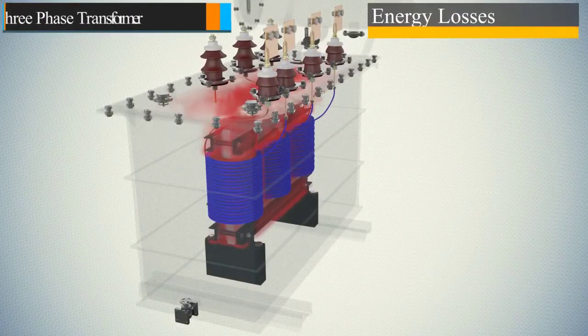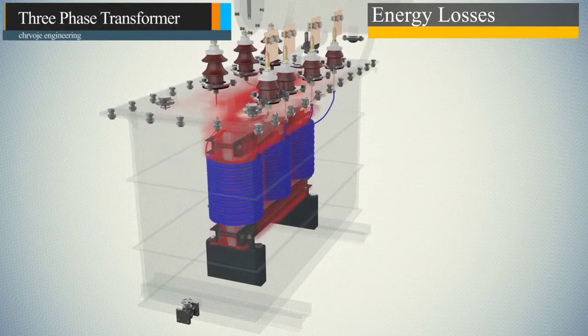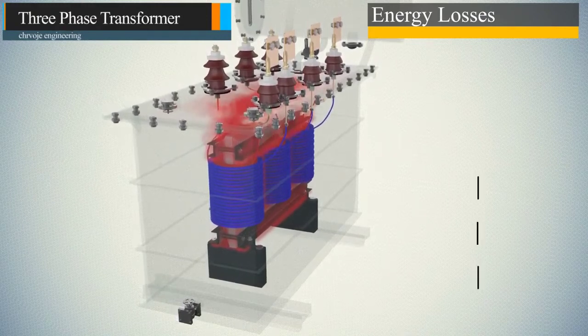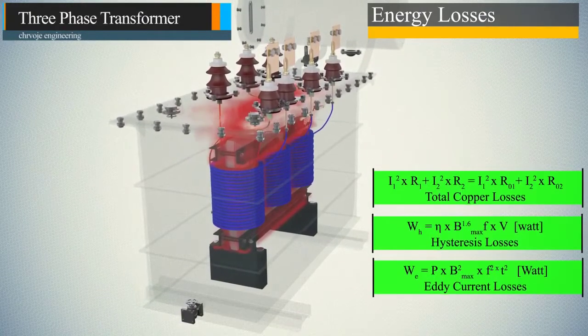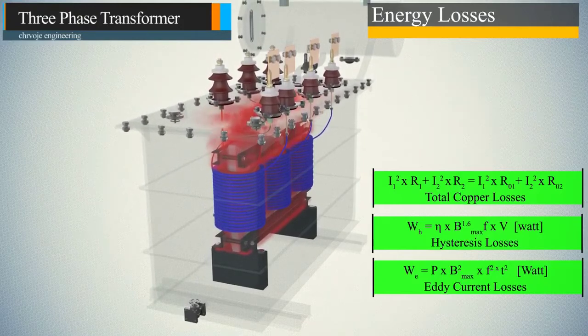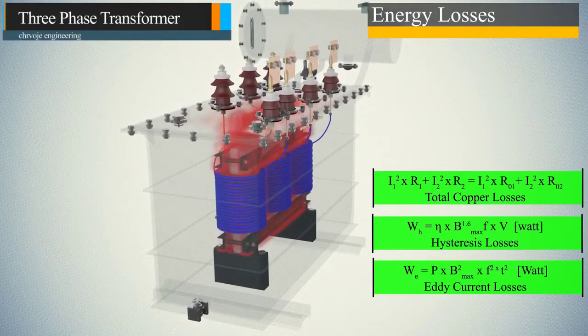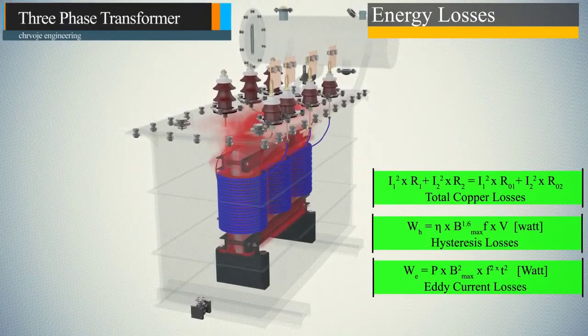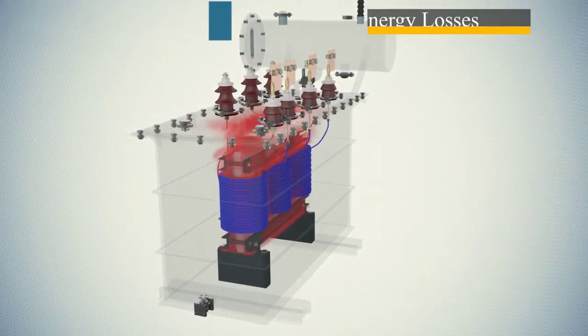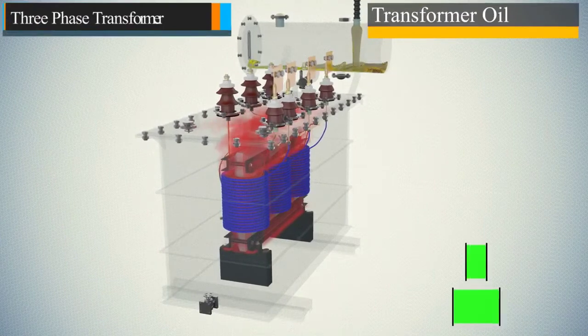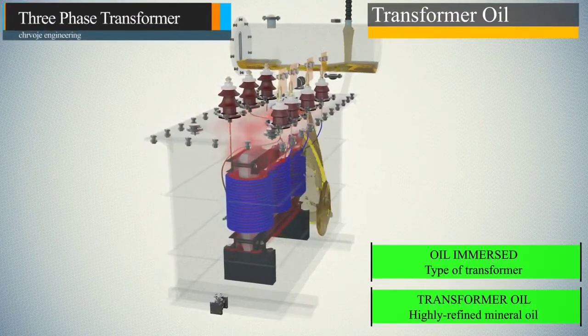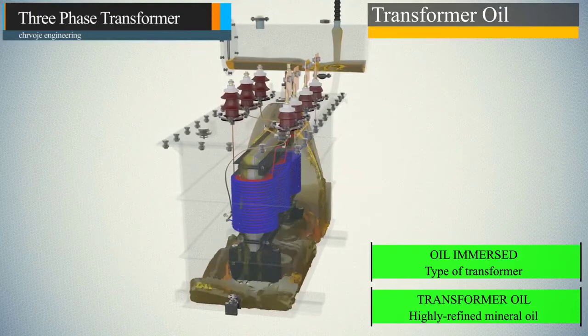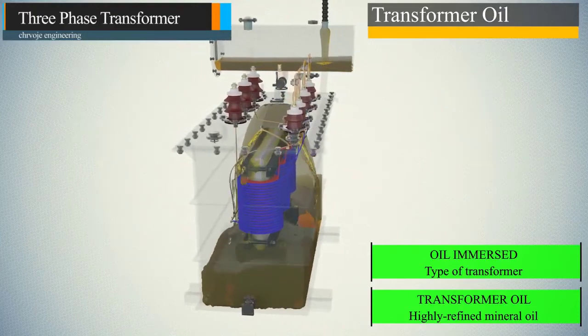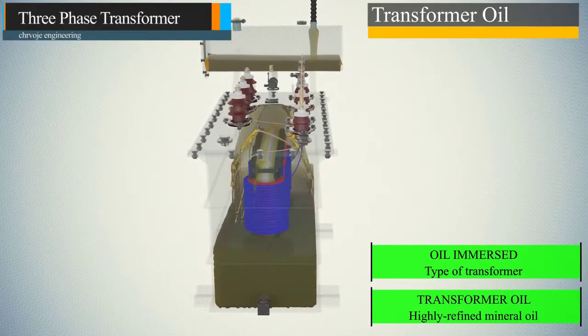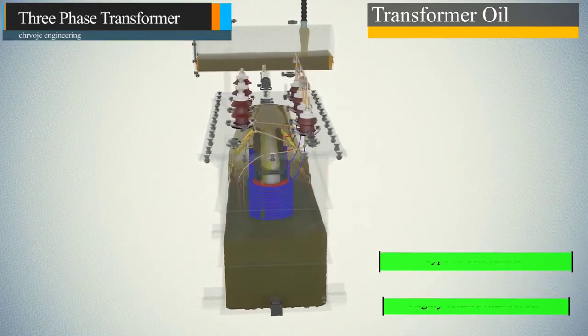While transferring power from primary to secondary windings in the transformer, various energy losses happen, like eddy current loss, hysteresis loss, and losses in copper. All these energy losses are dissipated as heat. To prevent this dissipated heat in an electrical transformer, we use transformer oil. Oil-immersed type of transformer are filled with oil through a conservator and Buchholz relay. Transformers' oils are usually a high refined mineral oil. Primary functions are to insulate and cool the transformer.